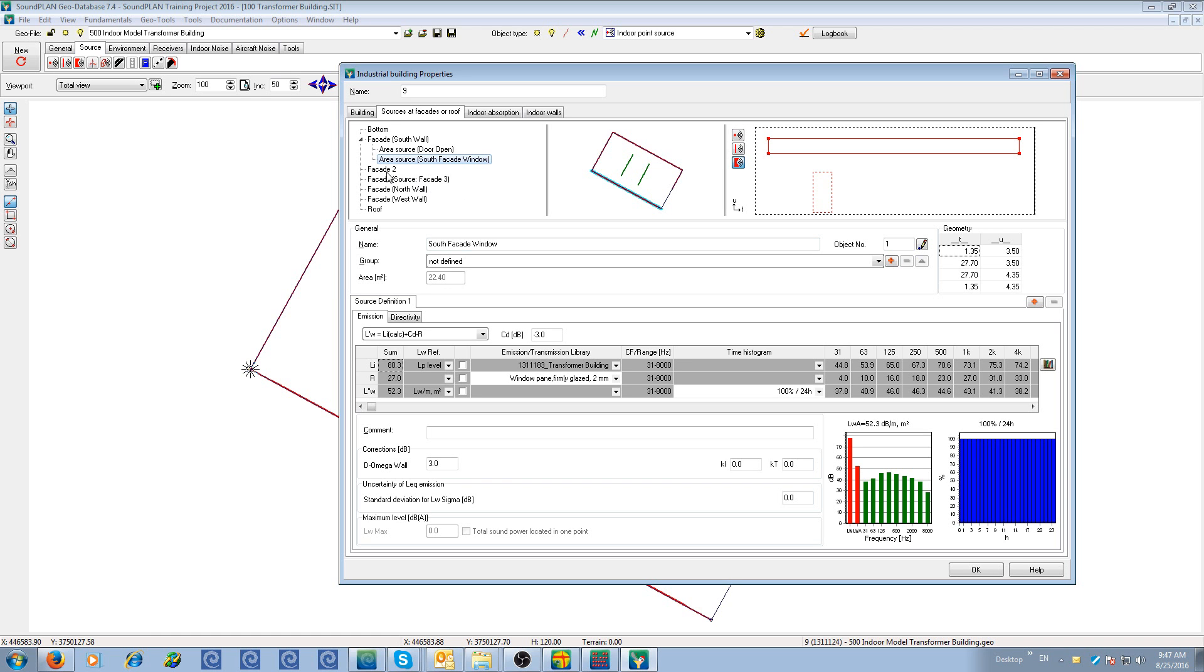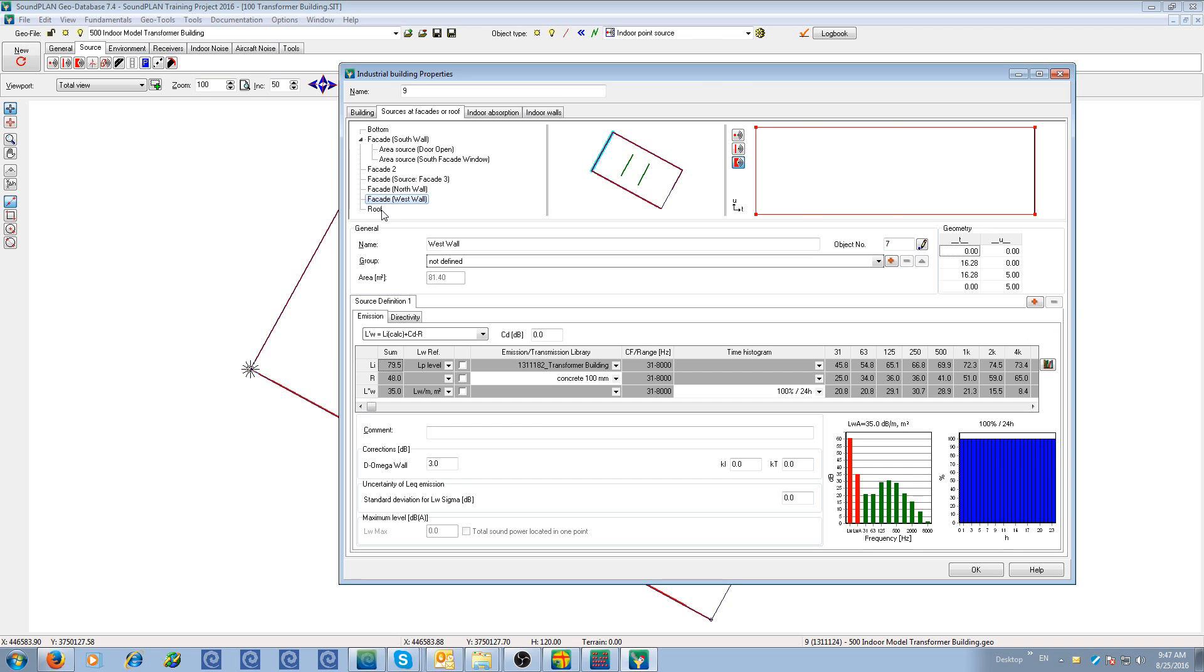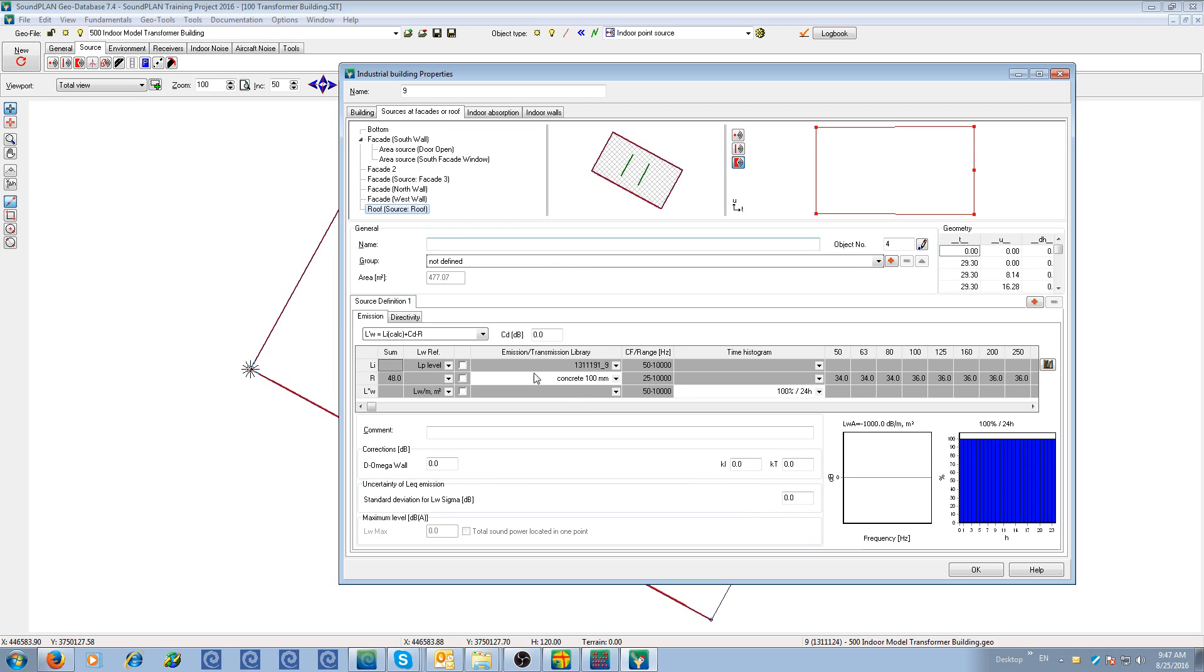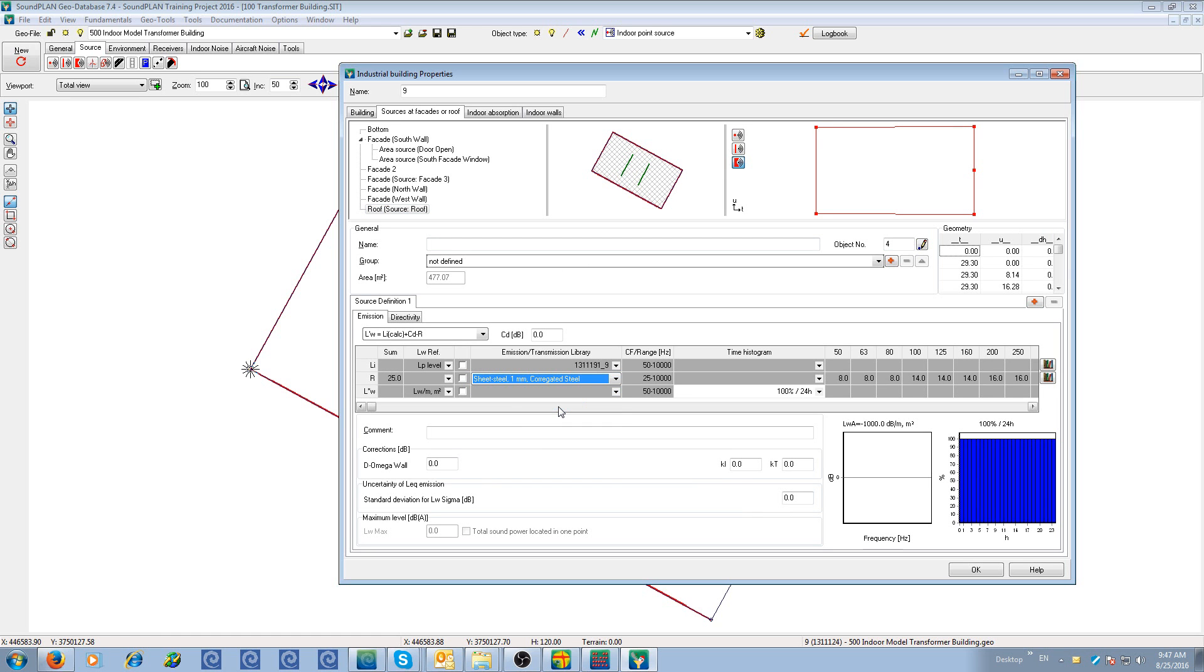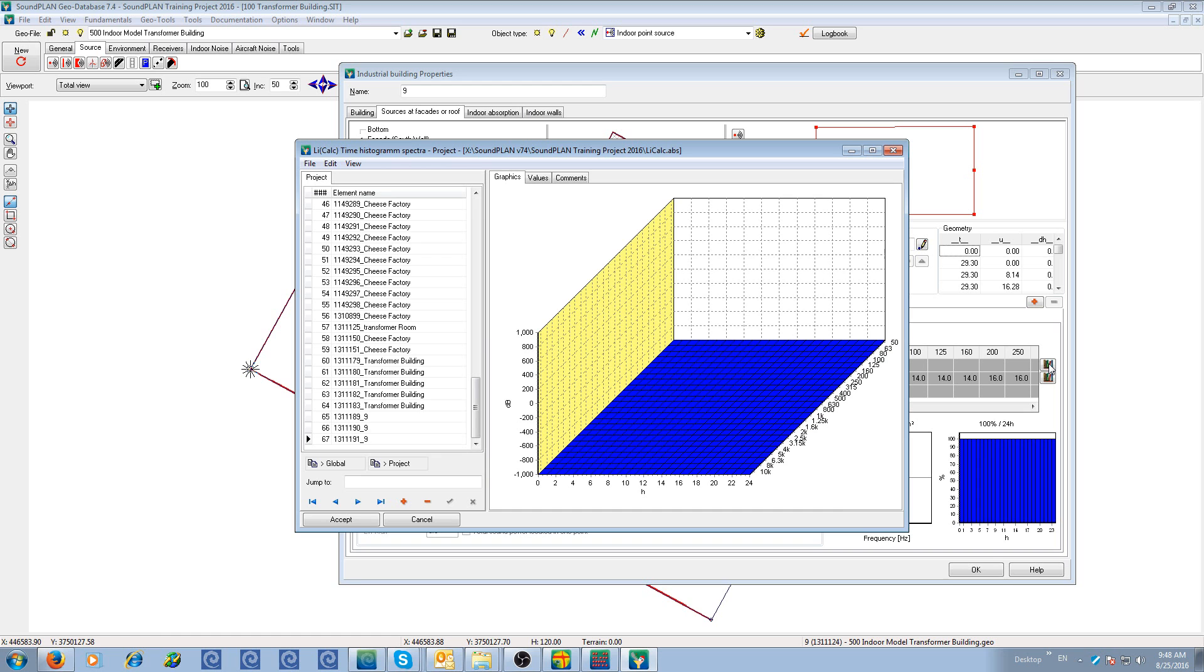So here we have multiple sources defined, north side, and then also the roof. Let me show you the defined facade as roof. Here we could set up that this would be, for example, corrugated steel with some insulation. So here again, it would calculate the interior noise level. And then it calculates the exterior sound power level on the outside. This library definition will set a source inside that library or source spectrum.